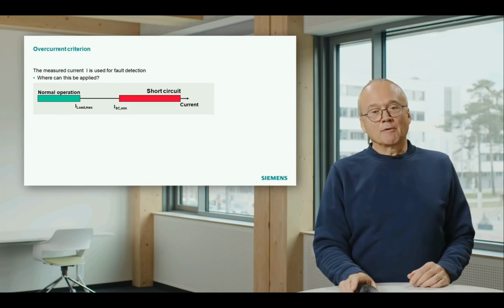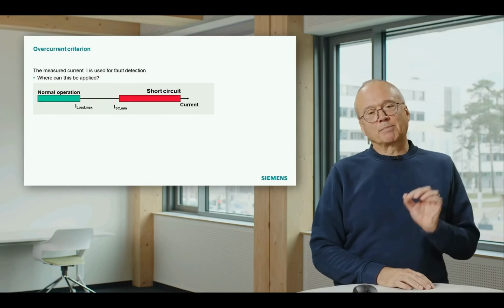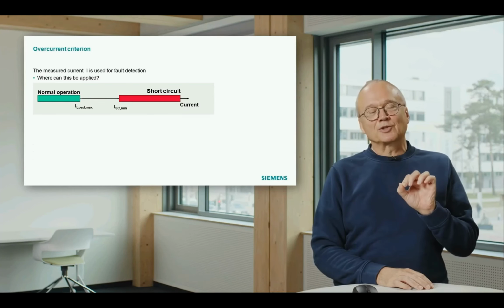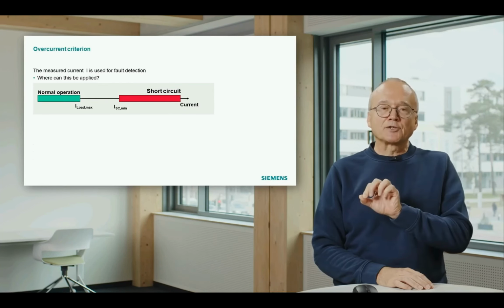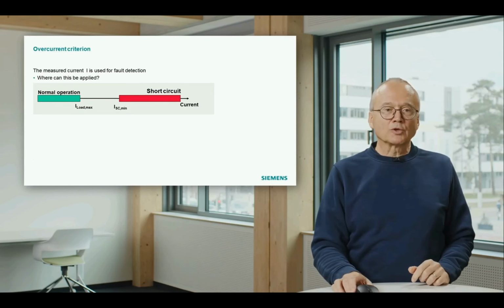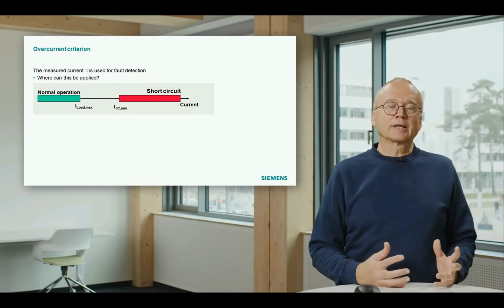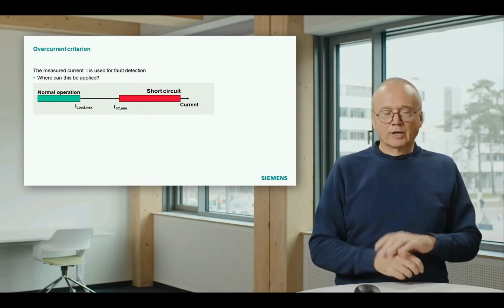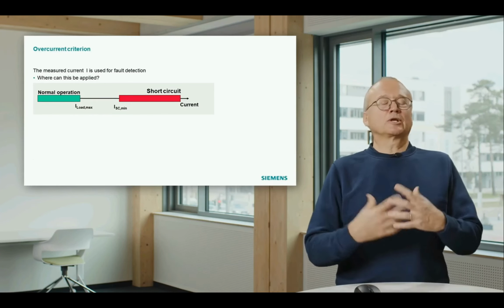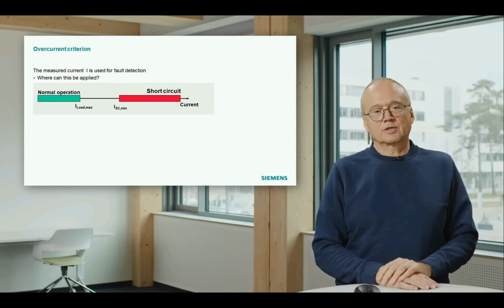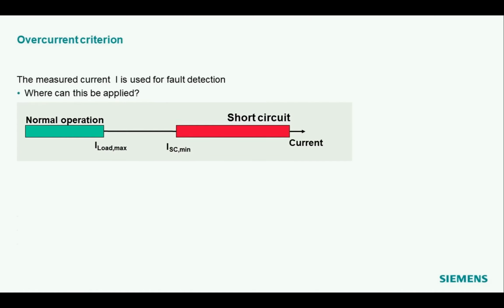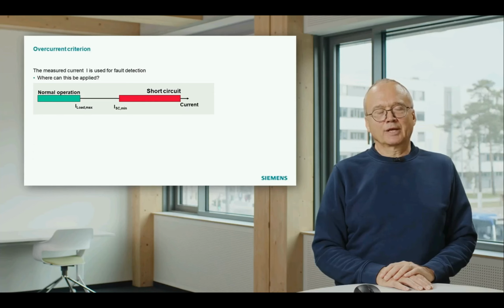That is always required to dimension the cross-section, for instance, of the cable. That is the maximum current at the right-hand side, but we are of course not interested only in short circuits with the maximum current. We must also take into account short circuits where lower short circuit currents are flowing, because there is some fault resistance involved, or not all generators are operating, or whatever. And with these considerations, we end up with a minimum short circuit current we want to catch.